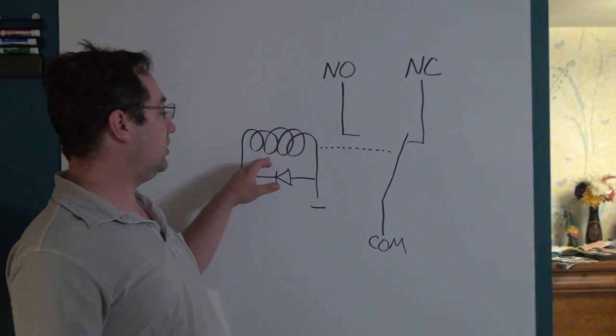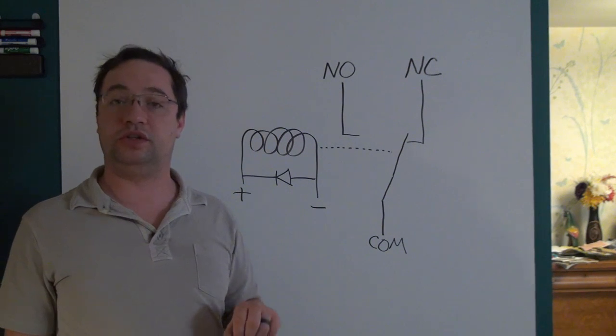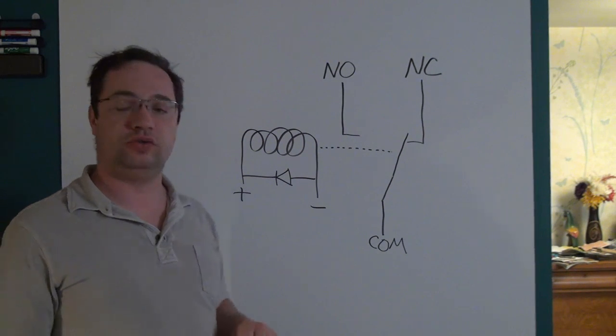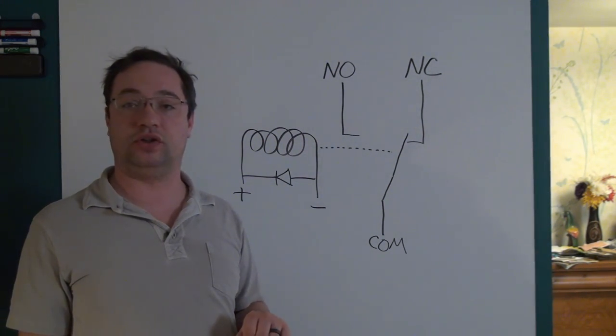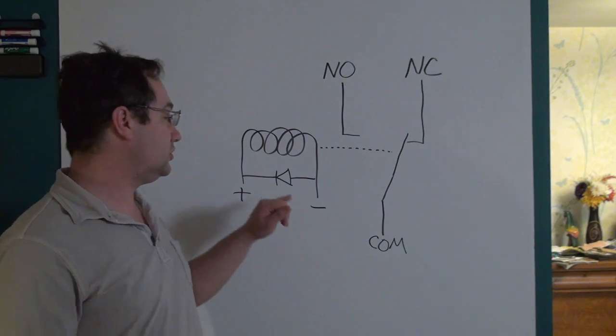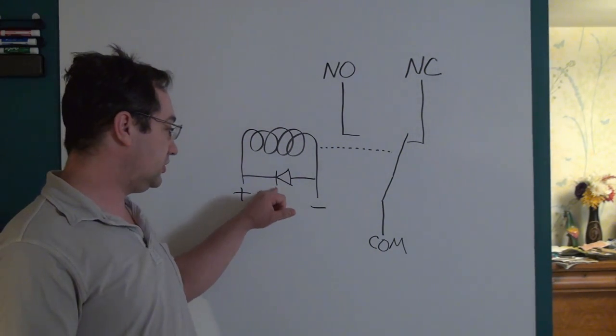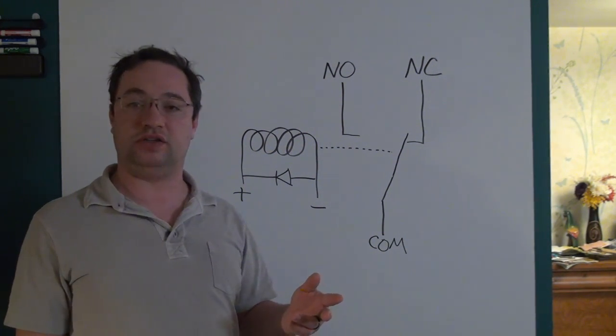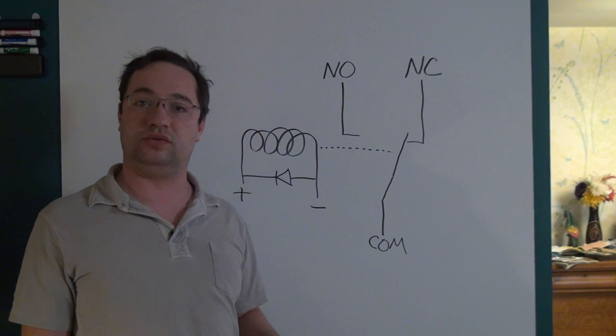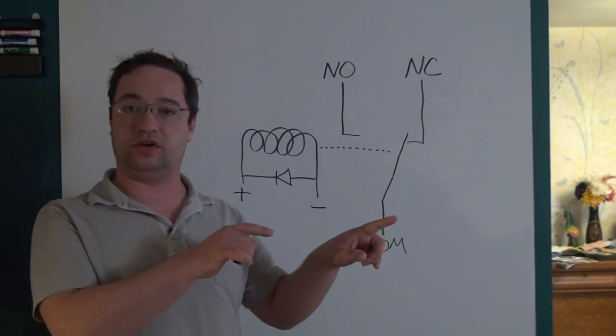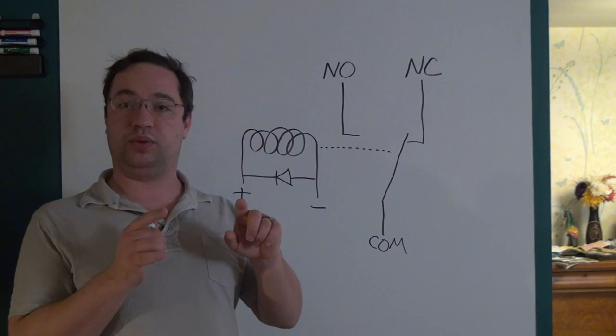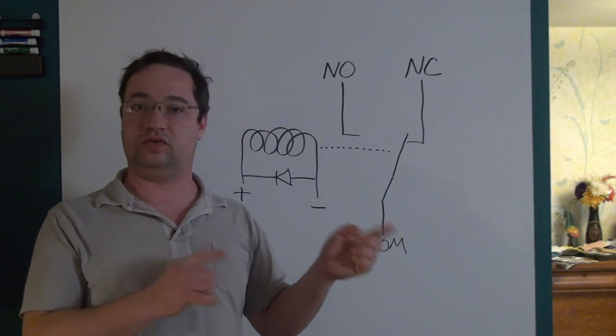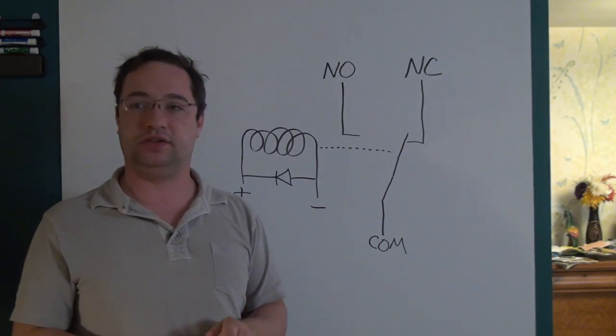If the relay does not have a diode built in — some DC-only relays will have it built in — you need to install this diode externally, because you will destroy things on a DC relay without it. AC relays don't need this diode because whatever is driving the AC relay will be tolerant of a spike, plus the field inside the coil works its way back and forth due to the AC sine wave.